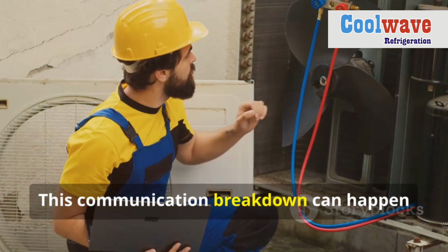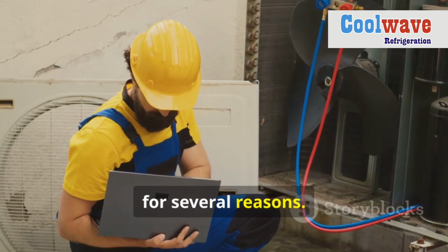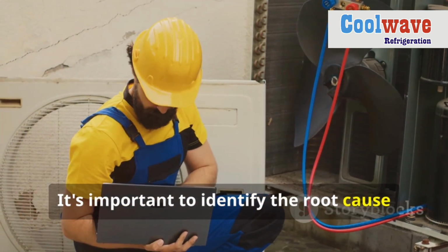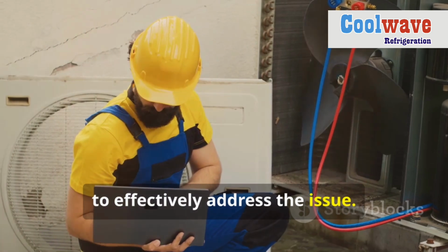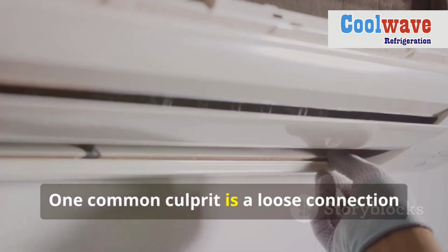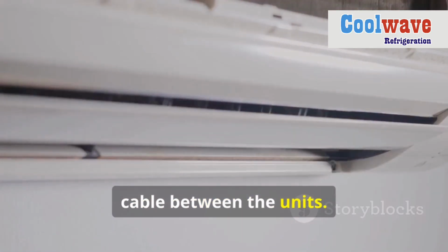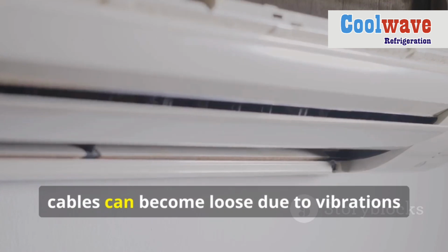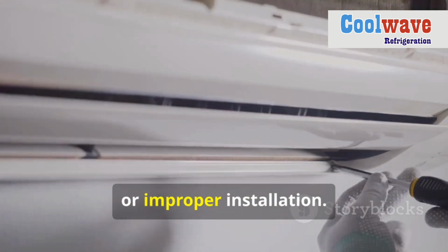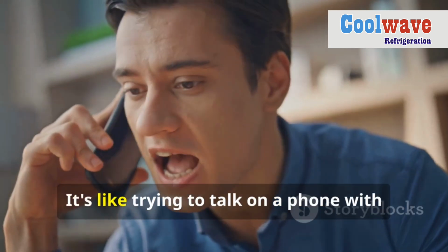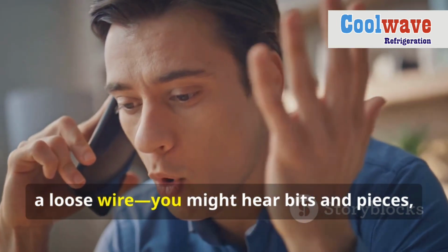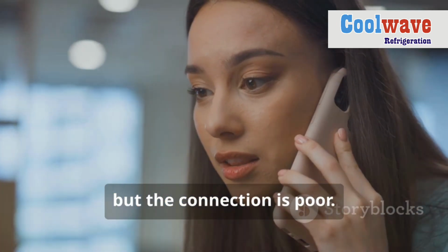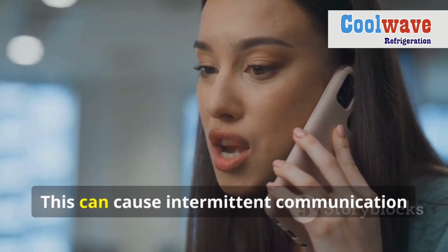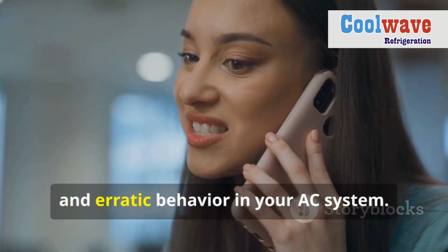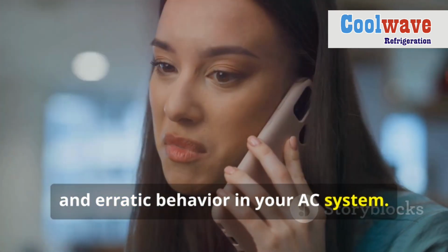This communication breakdown can happen for several reasons. It's important to identify the root cause to effectively address the issue. One common culprit is a loose connection cable between the units. Over time, cables can become loose due to vibrations or improper installation. It's like trying to talk on a phone with a loose wire. You might hear bits and pieces, but the connection is poor. This can cause intermittent communication and erratic behavior in your AC system.